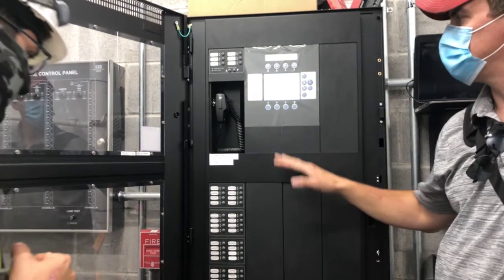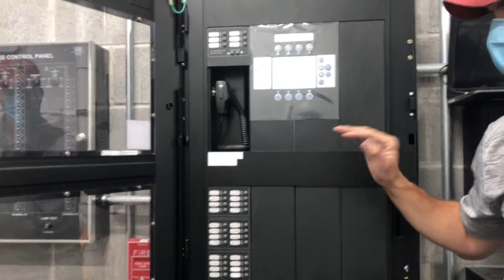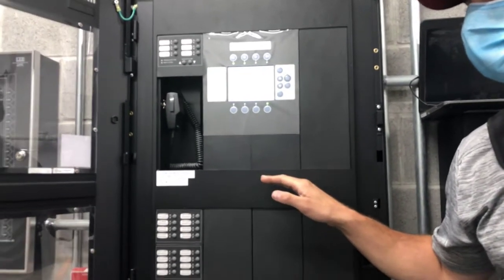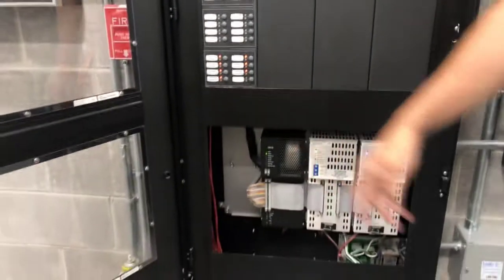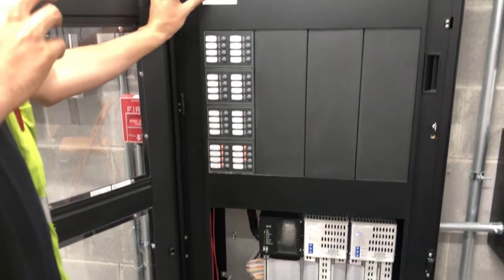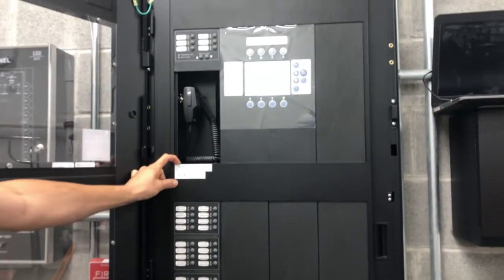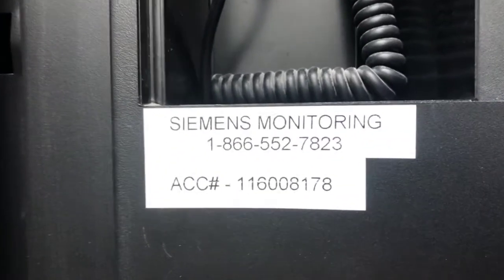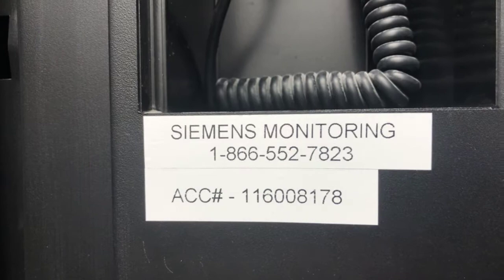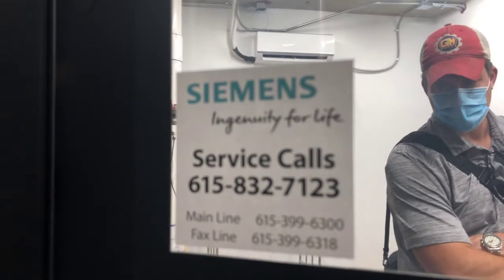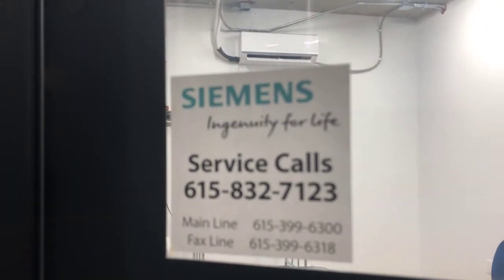So me calling into Siemens to put it on bypass or on test, and I still need to do this? Correct. Because there are 2 steps for this. What the account basically does is it stops the fire department from showing up on site. But locally, unless you bypass that, the alarm will still go off. So by you calling, it doesn't mean that the system will not do what it's supposed to. Okay. And this is for stopping the system from working, basically.